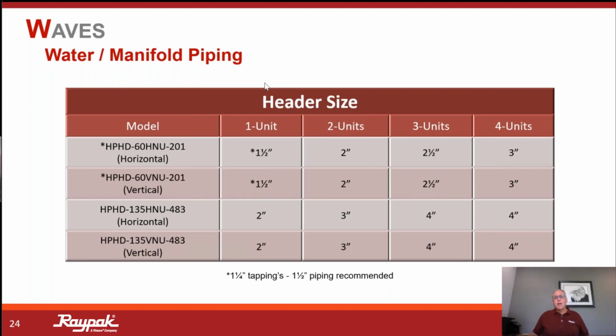Header size, again, not necessarily in the manuals, but in our piping diagrams, in keeping with how Raypak does things, you can go to raypak.com, go to our piping diagrams, and in the upper left-hand quadrant of those diagrams, you will see those header sizes. So if I wanted 2 units that were the 135,000 BTU horizontal, I would need a 3-inch header, okay?